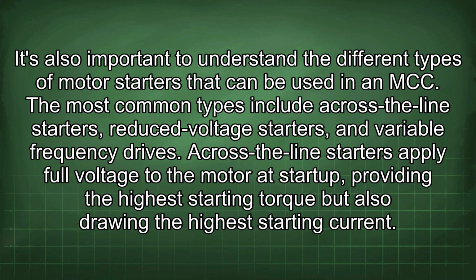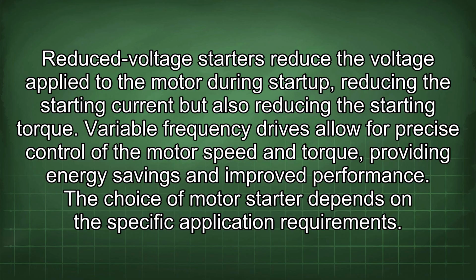It's also important to understand the different types of motor starters that can be used in an MCC. The most common types include across-the-line starters, reduced voltage starters, and variable frequency drives. Across-the-line starters apply full voltage to the motor at startup, providing the highest starting torque, but also drawing the highest starting current. Reduced voltage starters reduce the voltage applied to the motor during startup, reducing the starting current but also reducing the starting torque. Variable frequency drives allow for precise control of the motor speed and torque, providing energy savings and improved performance. The choice of motor starter depends on the specific application requirements.